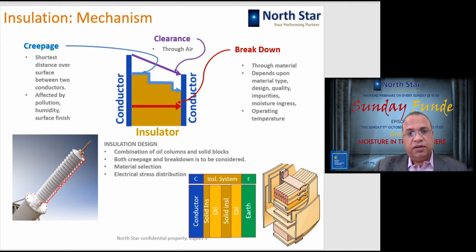Third, another important way of insulation breakdown or failure is creepage. Creepage happens through the surface, so that is the shortest distance over the surface between the two conductors, and this creepage is affected by the environmental condition to which it is subjected, especially when the insulation is facing the external environment, like in the case of bushings. So pollution is affecting it, humidity is affecting it, and of course the surface finish has an adverse effect on the creepage ability of the transformer.